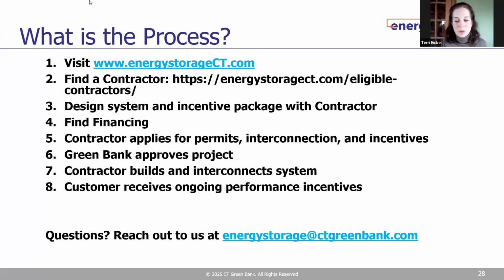Steve wanted to know if you pay the standard supply rate to charge the battery. If you have a grid-tied battery that does not charge from solar, it charges directly from the grid, so yes, you pay your standard rates to charge the battery. That's why ideally you're doing that at nighttime, when demand charges are lower, and if you have time-of-day rates, your kilowatt-hour energy rate is lower. So you do pay to fill it, and then when you use it on site during a discharge, it'll serve your building's load before anything goes off to the grid.